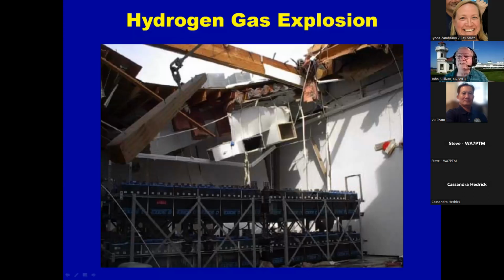All right, here's a picture of a facility. It used to be a computer data center with a battery room and emergency generators in Sacramento, California. The company vacated the building and moved out the computer equipment, but they left the battery backup system in place. The ventilation for the battery room appeared to be tied to a hydrogen monitoring system, which is a common practice, and the hydrogen sensor was actually alarming when emergency responders arrived at the scene after the explosion.